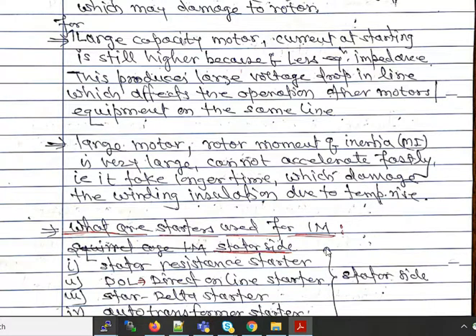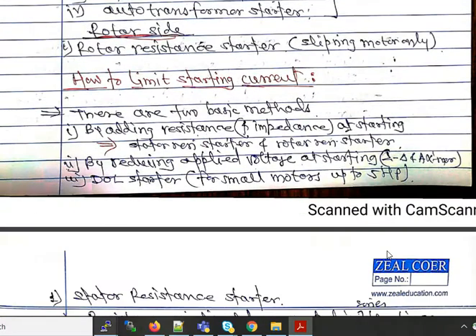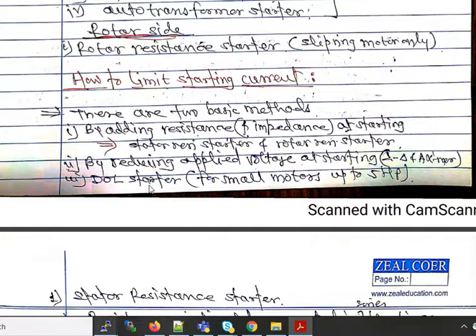What are the types of starters used for the induction motor? On the stator side: stator resistance starter, DOL (Direct On Line) starter, star-delta starter, and auto-transformer starter. On the rotor side: rotor resistance starter, used for slip ring motors only. There are two basic methods to limit starting current: adding external resistance in the stator circuit, and reducing the applied voltage. The DOL starter neither adds resistance nor reduces voltage and is used only for small motors up to 5 hp.